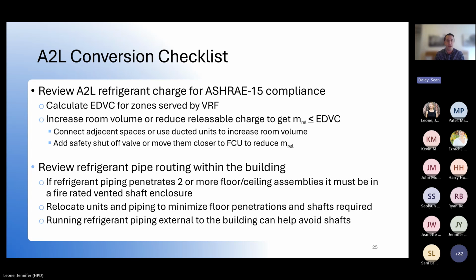You can do that one of two ways. You can either increase the EDVC by increasing the room volume, connecting adjacent spaces, or using a ducted unit to serve multiple rooms. The other method to help comply would be to reduce your releasable charge. The only way we can really do that is to get that isolation valve closer to the unit itself. That would help reduce our MREL and hopefully get it under the EDVC.